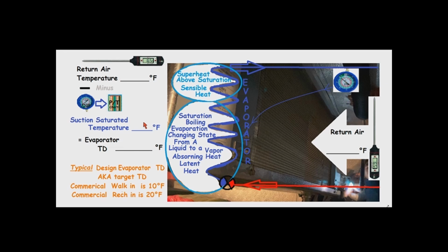Now, on a key note, it's important that anytime you're working at a walk-in cooler or a walk-in freezer, you wait there with it, babysit it for the temperature to come down to set point. You want it to cycle off naturally. So if I have a walk-in cooler and it's set for 35 degrees, I want to sit there and wait for that cooler to get to 35, or maybe it's set for 38. It definitely should be below 40, but whatever it's set for, I'm going to wait for it to cycle off. And that may be very time consuming.